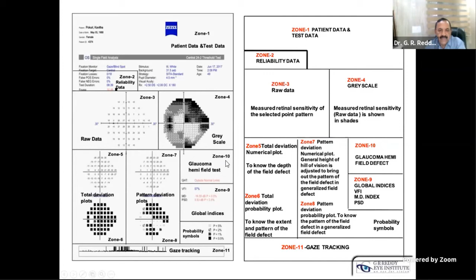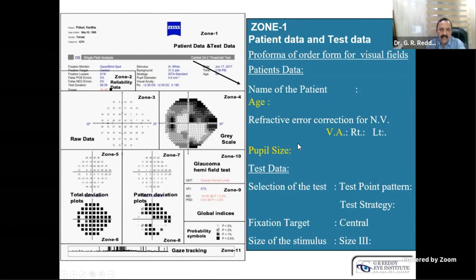So zone 1 is nothing but what we fed to the computer. Verify whether the patient data is properly entered, especially the age of the patient, pupil size, and visual acuity. Then test data. What test you asked for, 24-2 or 30-2 or 10-2, whether it is properly taken or not, what strategy you selected, what fixation target you fixed. Everything you have written in the pro forma will be fed in and verified, and whether it is properly fed to the field analyzer or not.